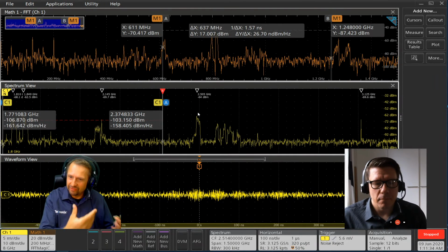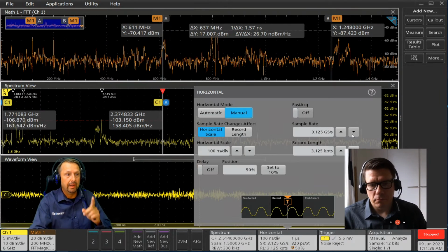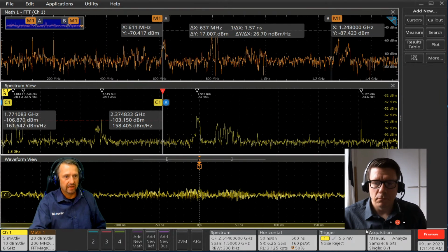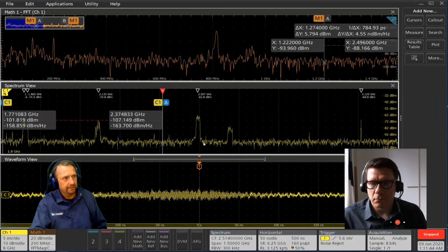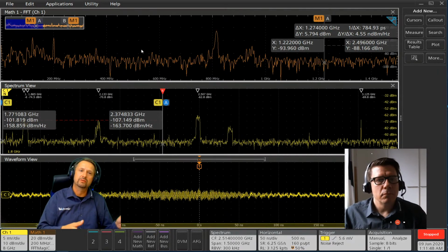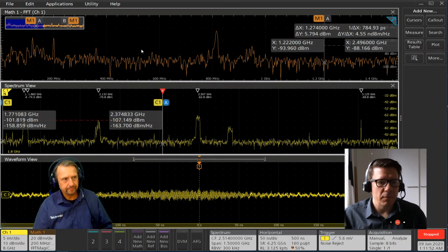And again, it's very simple. You need to increase the sample rate. So if I increase the sample rate one step up to 6.25 and I run this one, of course it was not. Now I have it here, but there's nothing around 600. So it's related to undersampling. Okay, so basically you were undersampling the signal.